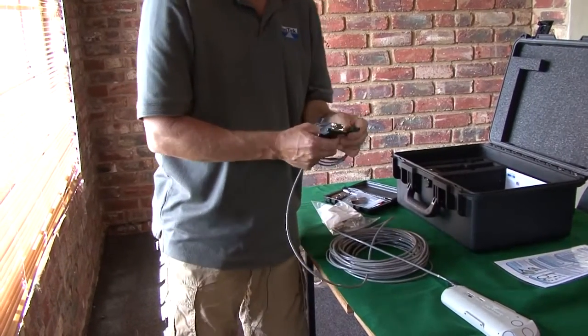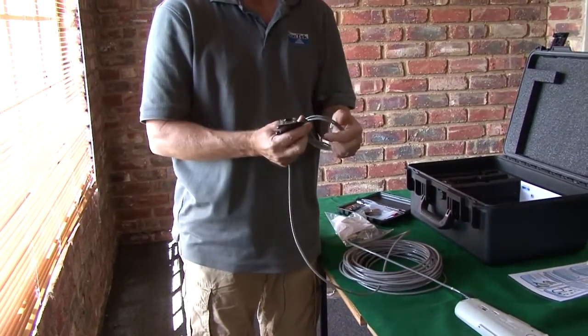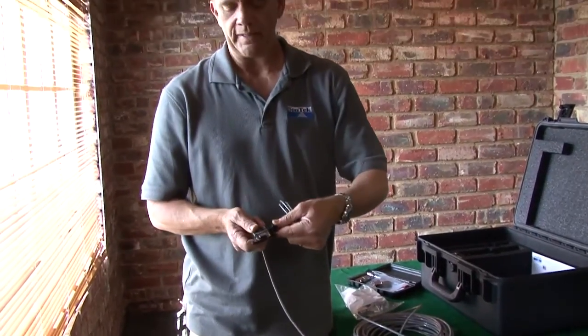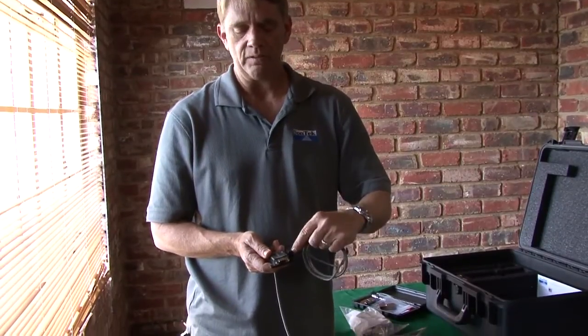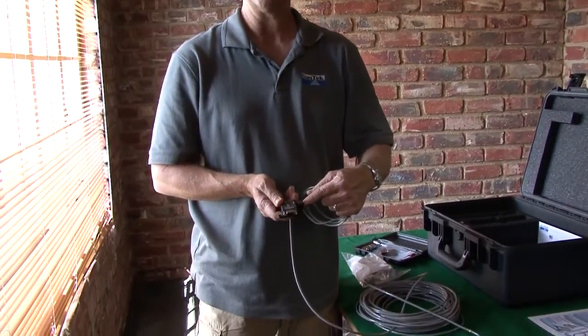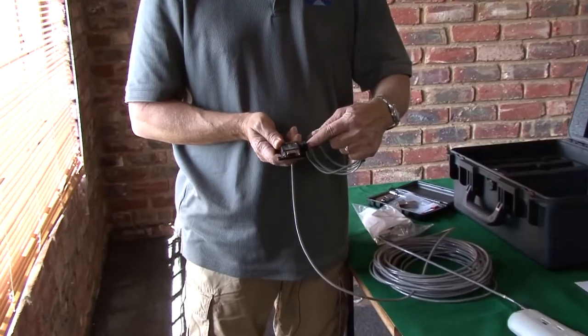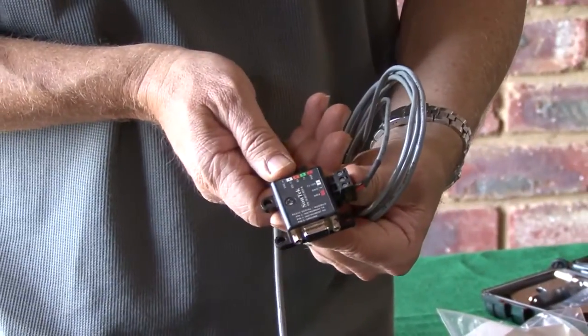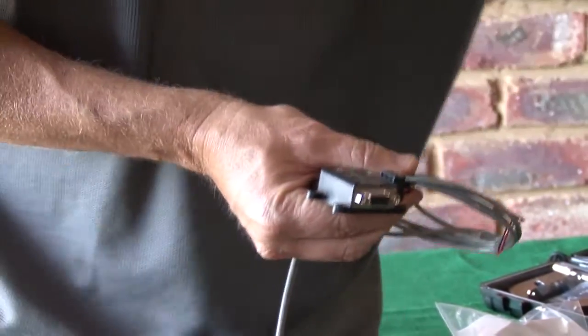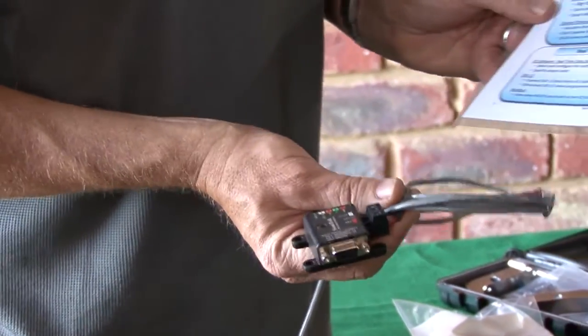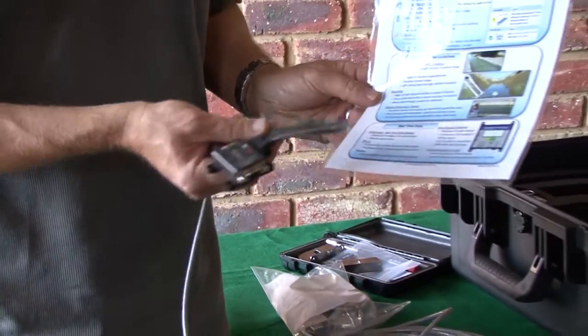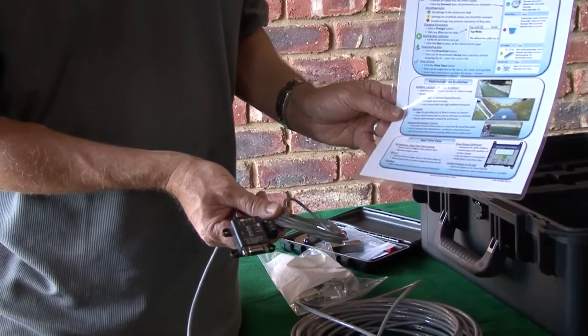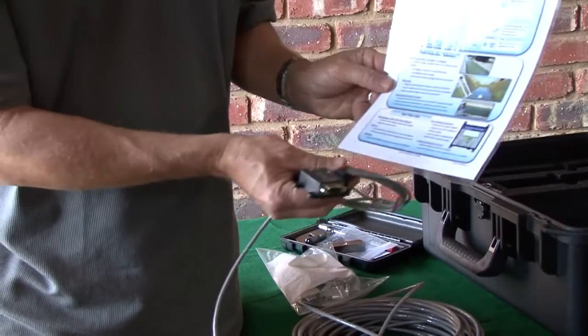Depending upon how you connect power to it, I have a little power cable here. It actually operates between 7 and 14 volts, but I can plug it in there. And this also will provide, if I'm using an SDI-12 data logger, this provides the SDI line. Everything's pretty well marked. If you order the real-time display, basically everything is in this little module here, with the addition of the display and the 4 to 20 outputs.